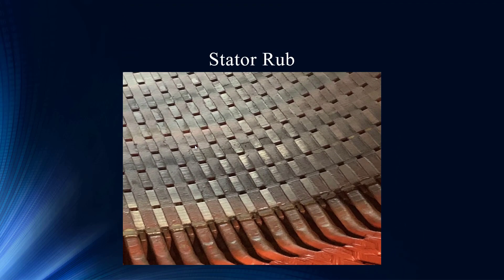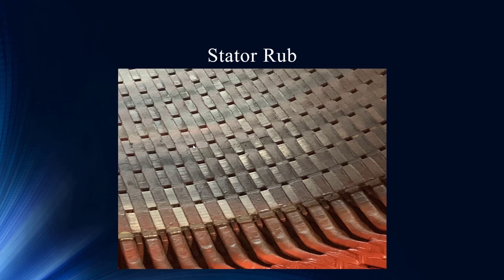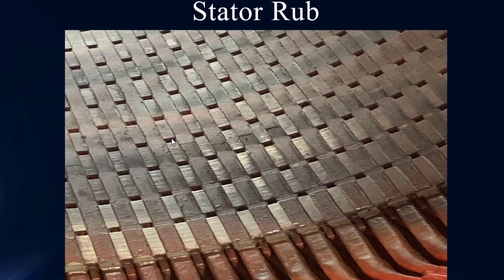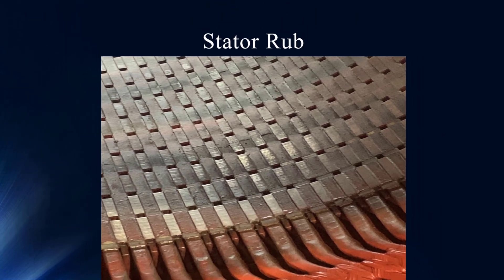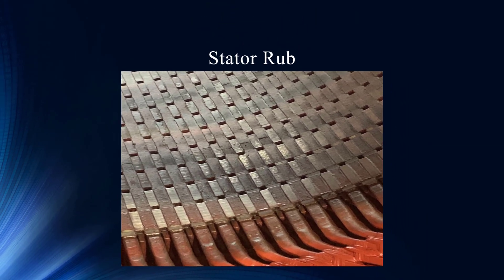You can also see the stator — the damage from the rotor rubbing against the stator. It doesn't look severe, and they're going to probably do some testing here. When they get this motor apart, they'll do core loss examinations of the stator iron, and hopefully they can save it. But if not, restacking and rewinding that stator becomes expensive.